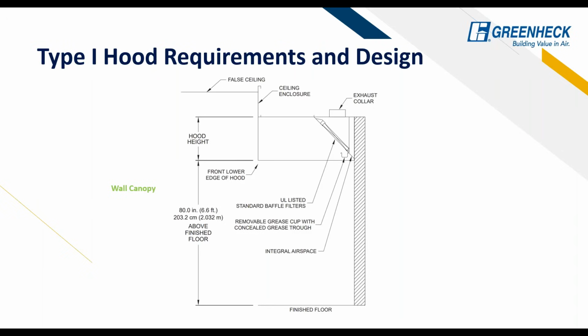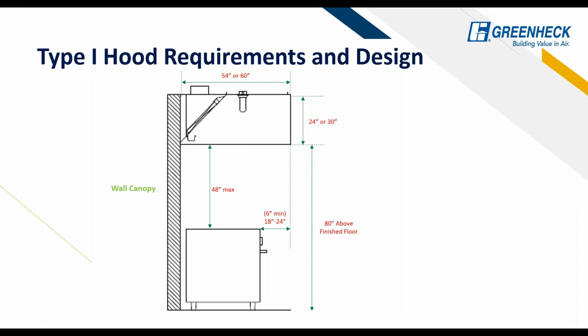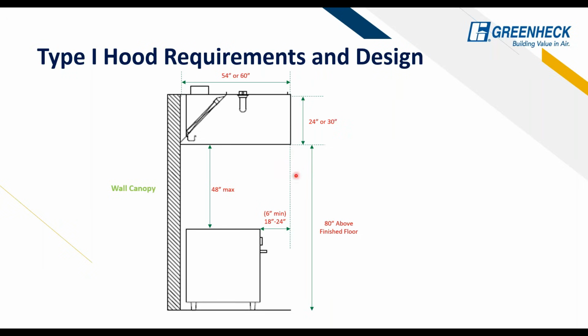So here is a typical hood. I'm actually going to go to the next slide here, showing some dimensions. So this is a typical setup with the hood. One other thing you need to be aware of is this requirement here: 48 inches max from the bottom lip of the hood to the top of the cooking surface. It needs to be 48 inches max to ensure that we're keeping that heat inside the hood.